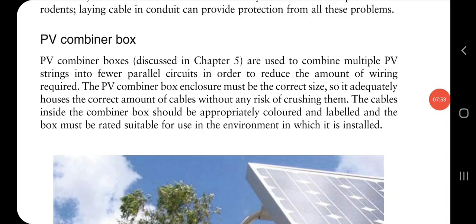Now next we will move on to the PV combiner box. As we know, the combiner box collects the cables from the PV arrays. All the cables from the arrays go to the combiner box. In the combiner box, it should be connected properly and be of a proper size. The cables which are coming in should be labeled and colored.